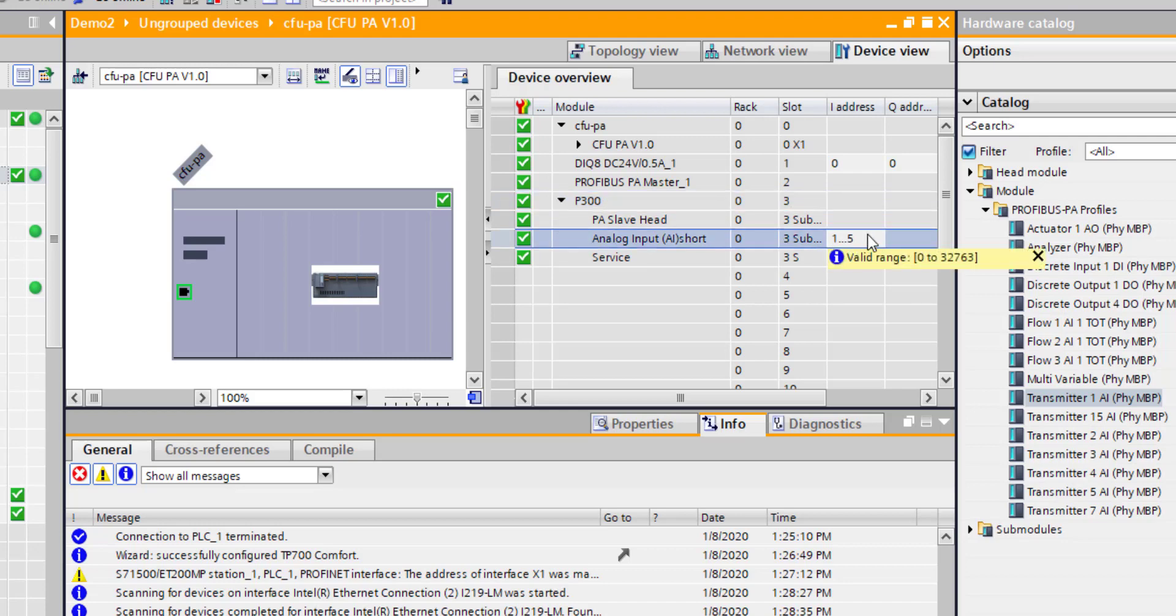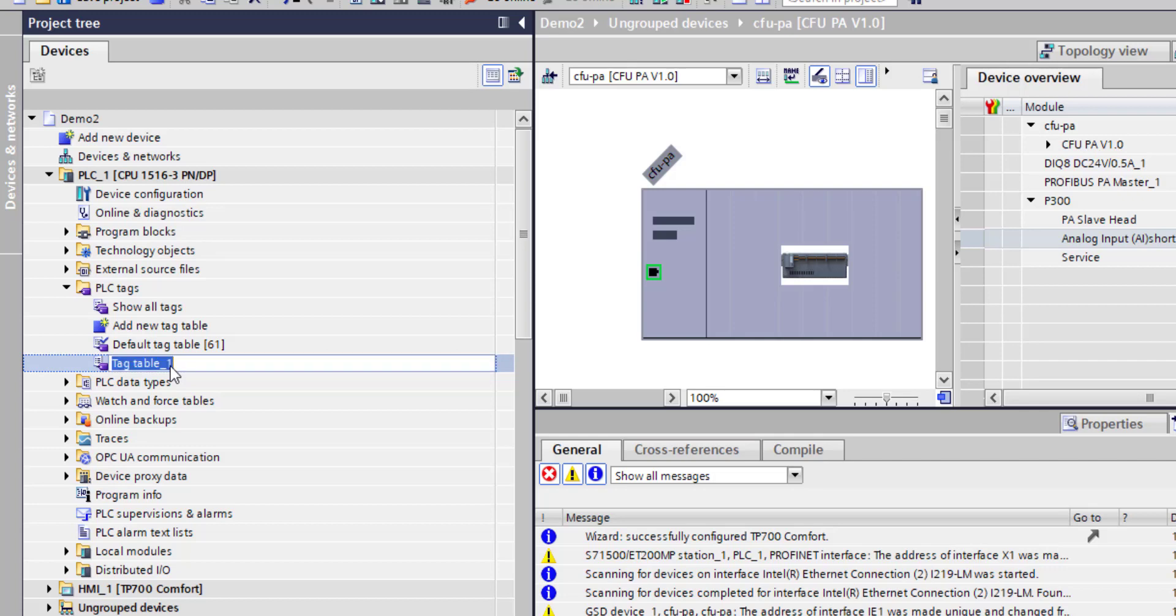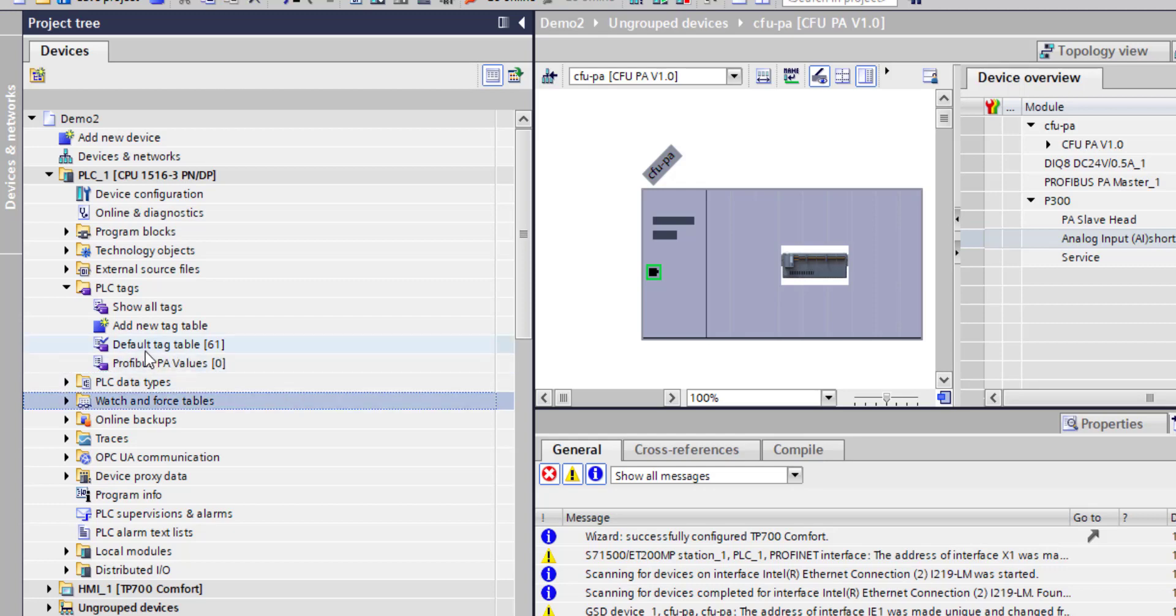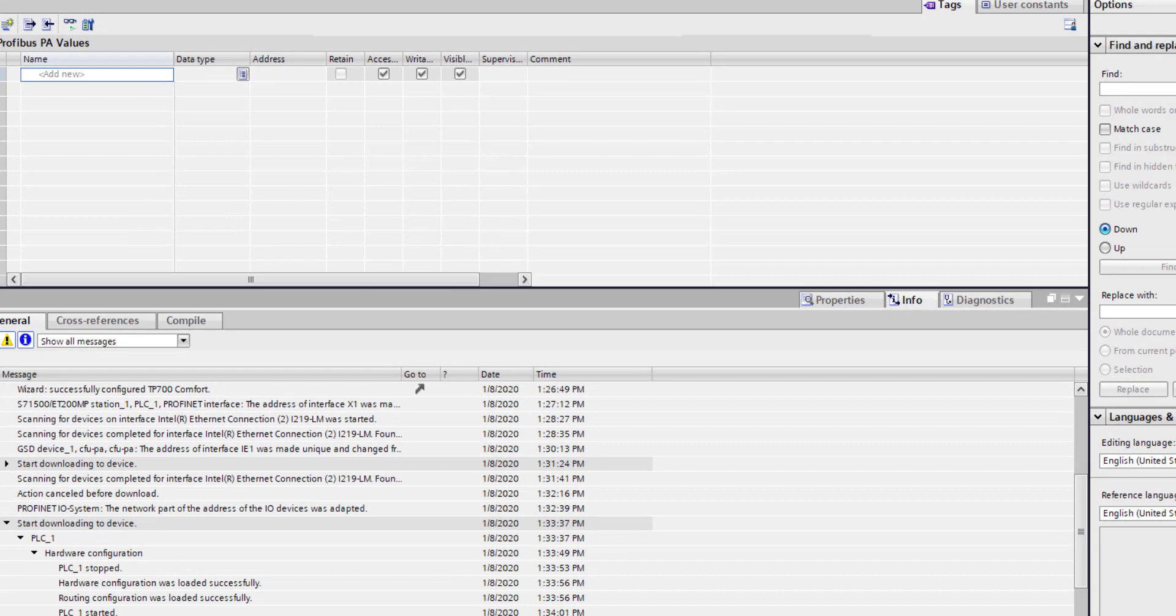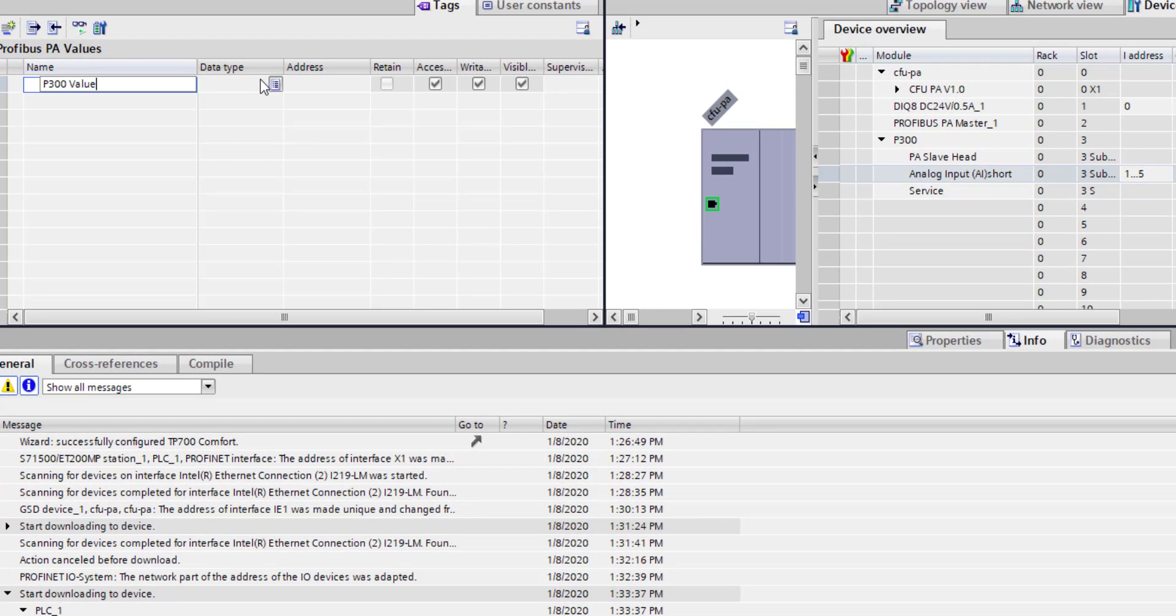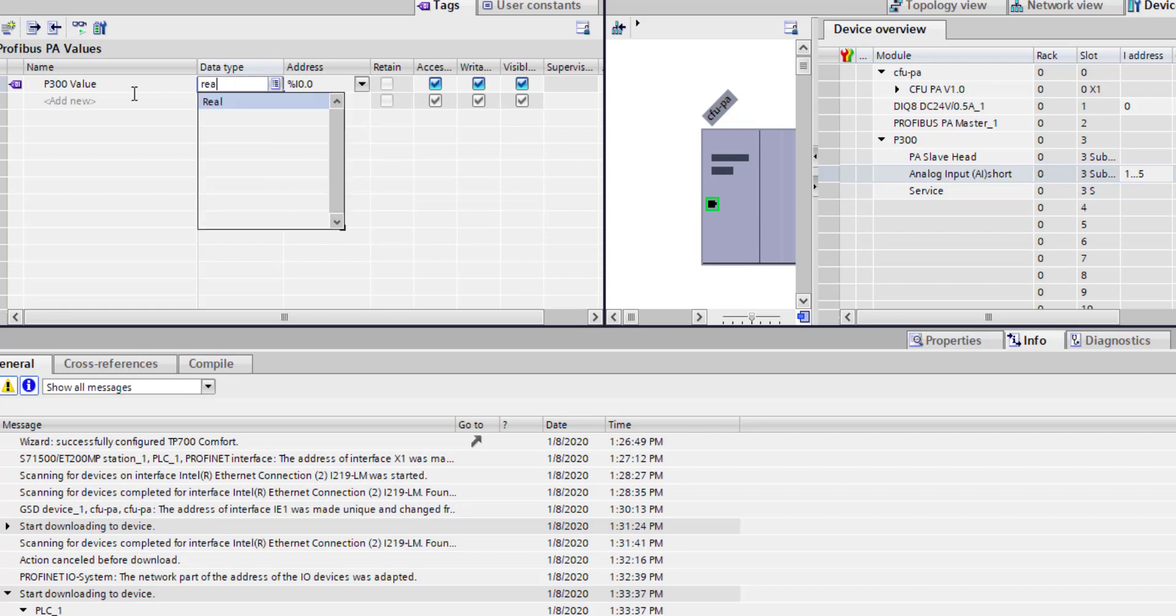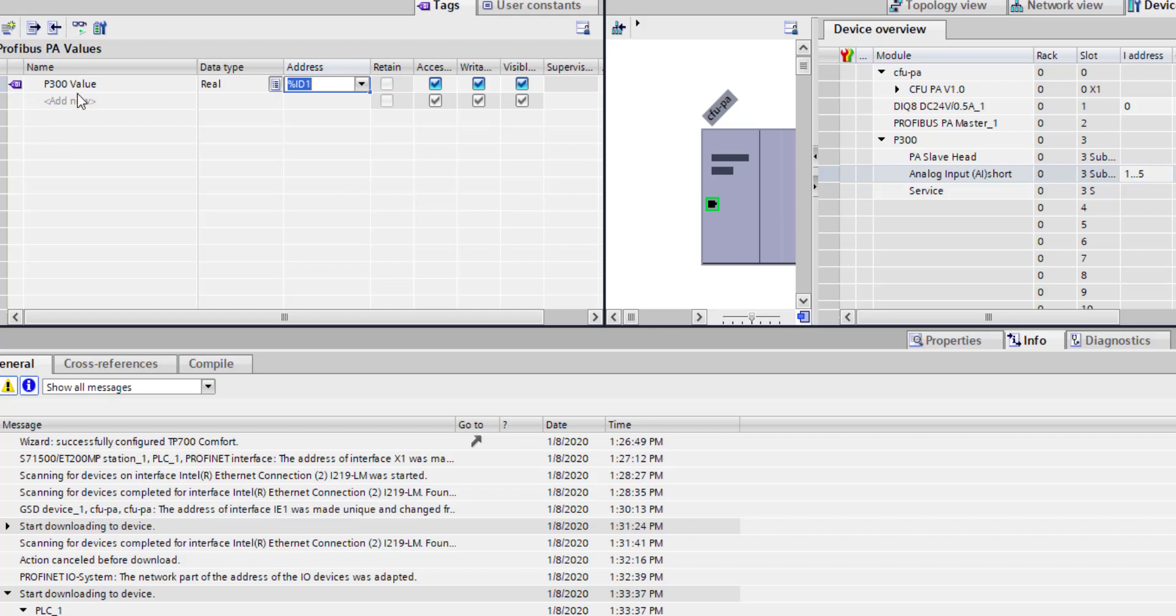This is a bit of a structure, so I can't drag and drop it from here. I've got to set some PLC tags. I'm going to add a new tag table. Remember to go offline. I'm going to call that PROFIBUS PA values. What you can do here if you've got a terrible memory like me, you can go split screen. I'm going to call this P300_value and it is a real, so it requires no scaling. I have to set the format - it's an input, it's a double, and if we have a look here, it's starting off at one.